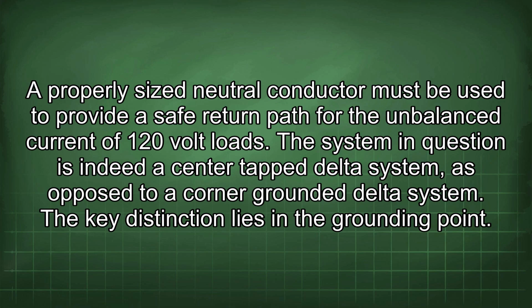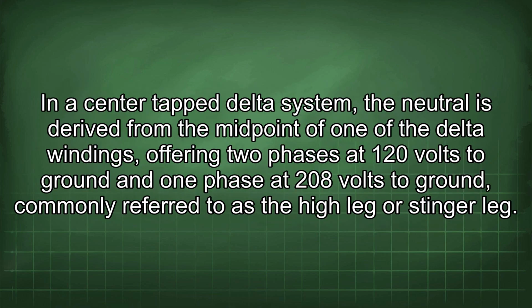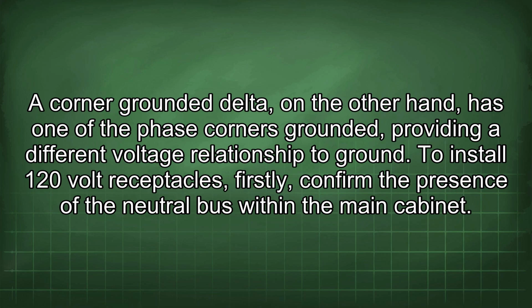The system in question is indeed a center tap delta system, as opposed to a corner grounded delta system. The key distinction lies in the grounding point. In a center tap delta system, the neutral is derived from the midpoint of one of the delta windings, offering two phases at 120 volts to ground and one phase at 208 volts to ground, commonly referred to as the high leg or stinger leg. A corner grounded delta, on the other hand, has one of the phase corners grounded, providing a different voltage relationship to ground.